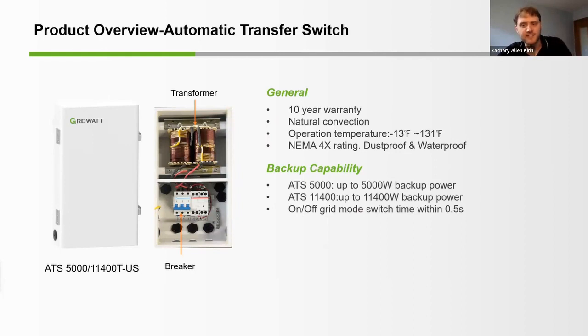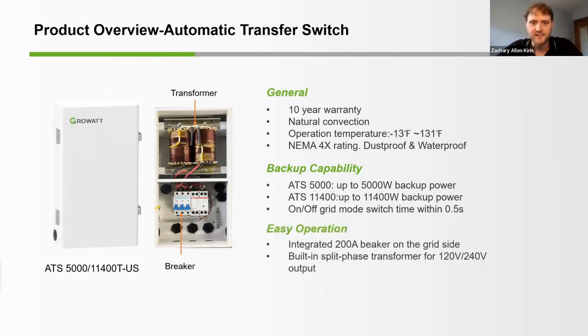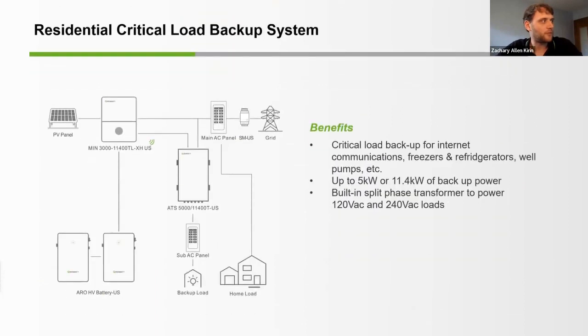The ATS features a built-in split-phase transformer for 120 volt loads and can handle a phase imbalance up to 3,000 watts. This device interfaces with the MIN inverter. We're going to discuss a little bit more about how this is important. This MIN inverter is what I would refer to as the V2 model. This is how we refer to it as Growatt. This is supporting the ATS. This is the V2 inverter. It features a grid output and also a load output. This is used for critical load backup for internet communications, freezers and refrigerators, even well pumps, up to 5 kilowatts or 11.4 kilowatts of backup power, and provides split phase power to the loads.